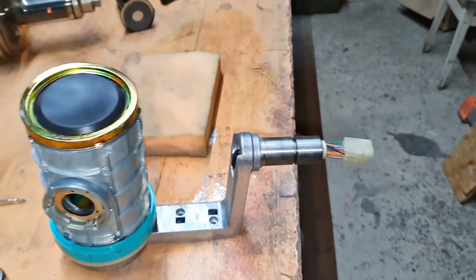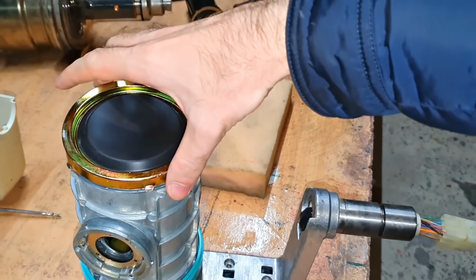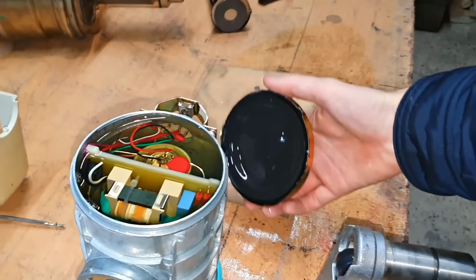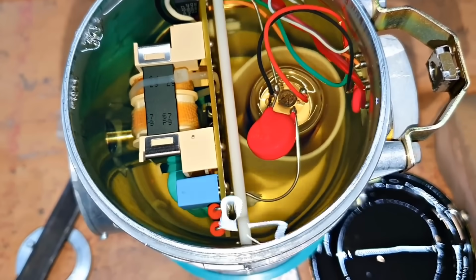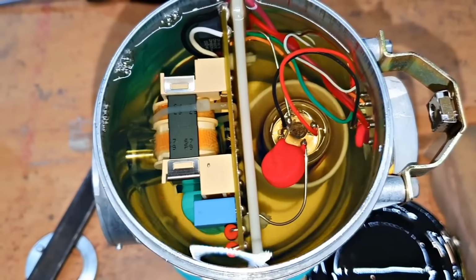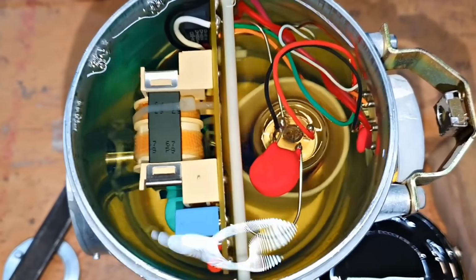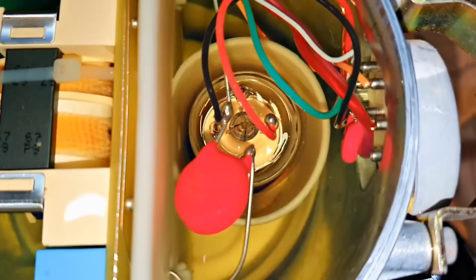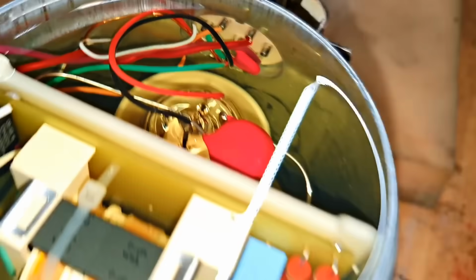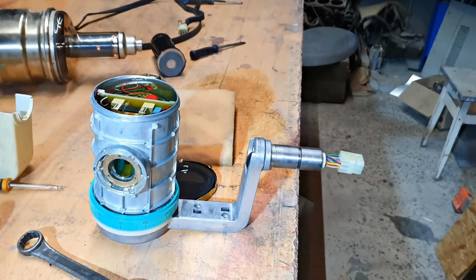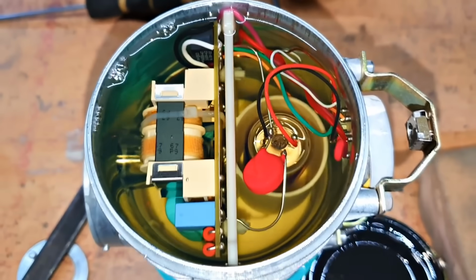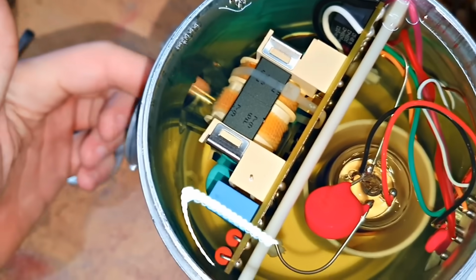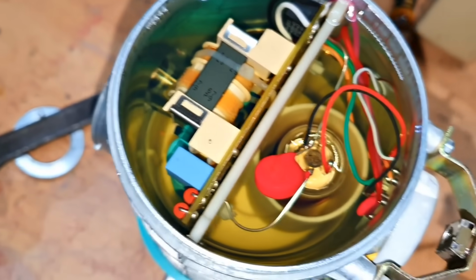For a start, we have to disassemble this device and see what is inside. When we opened the lid, we discovered that there is a hell of a lot of transformer oil. If I were you, I wouldn't throw it away. And there is the lamp itself. It can't work without oil, it's going to burn out. Why so? It's going to overheat. Interesting, there is a small window with no oil. No oil? See, that's the air channel. I can put my finger over here. Oh, in that hole? Yeah.